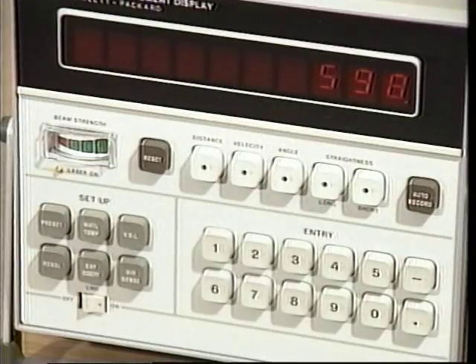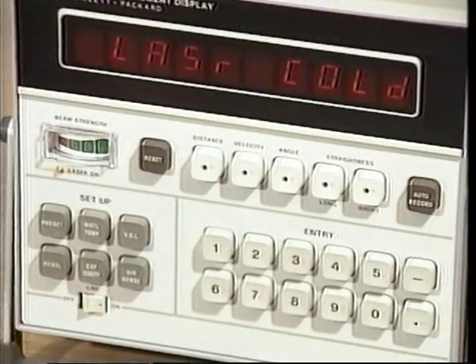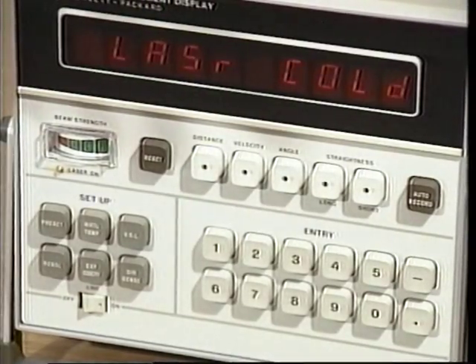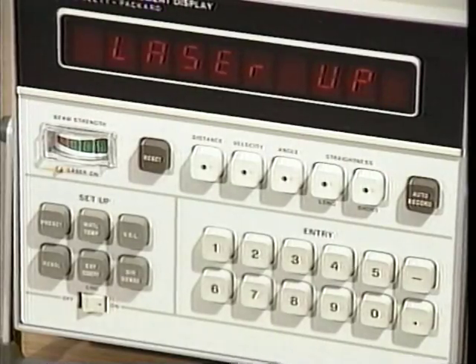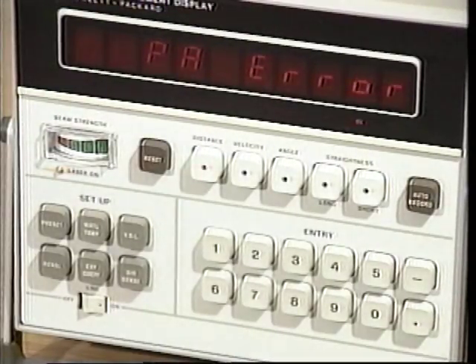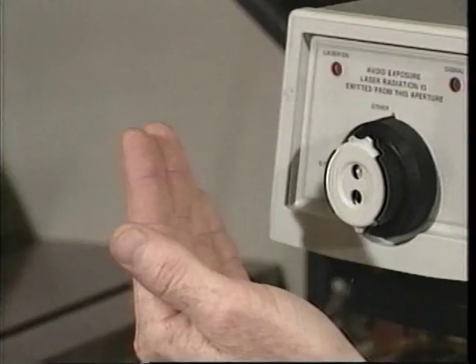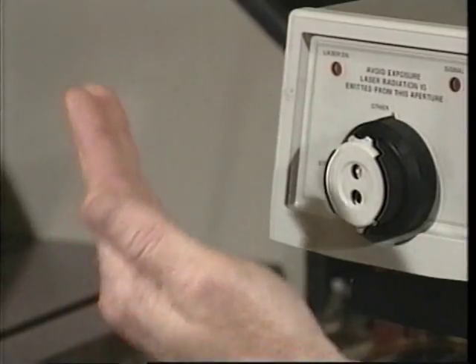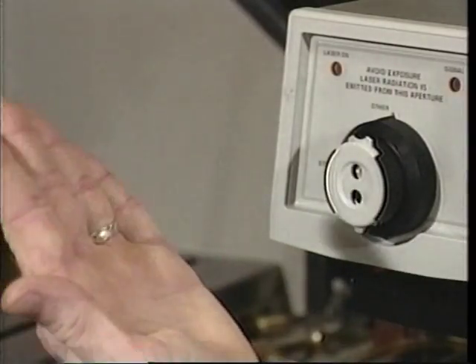During this warm-up period, the display will read laser cold. When the system is ready, the display will read laser up if the beam is being received by the detector, or path error if the beam is not being detected. The laser on indicator on the front of the laser head should now be lighted. Unless the laser beam aperture control is closed, the red laser beam should be visible.